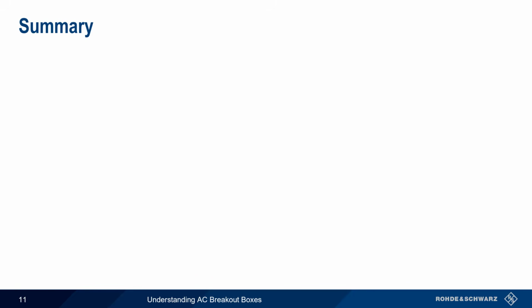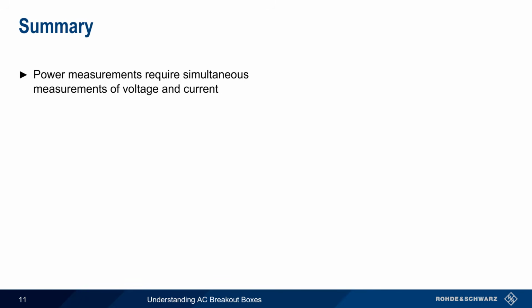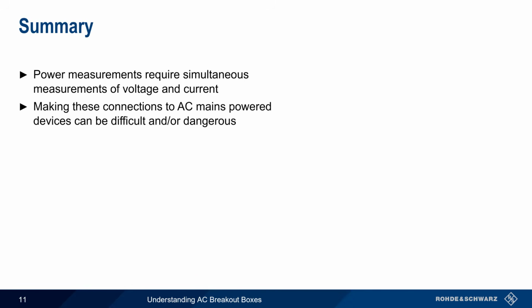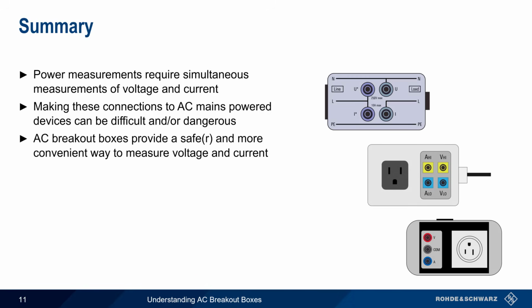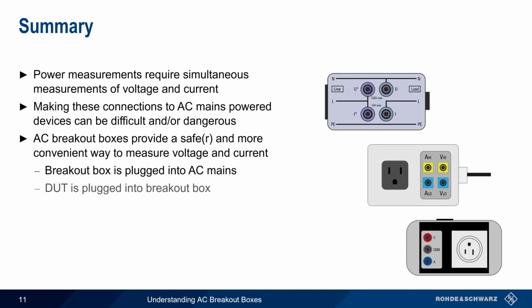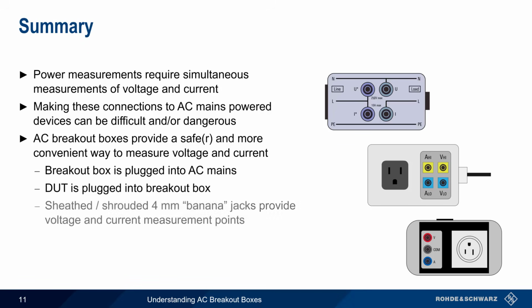Let's end with a brief summary. Power measurements require simultaneous measurement of both voltage and current. Various instruments can be used to perform these measurements, but making the measurement connection to AC mains powered devices can be both difficult and/or dangerous. AC breakout boxes are therefore used to provide a safer and more convenient way to make these voltage and current measurements on mains-connected devices. The breakout box is plugged into AC mains, the DUT is plugged into the breakout box, and sheathed or shrouded 4mm banana jacks can then be used for the voltage and current measurement points.